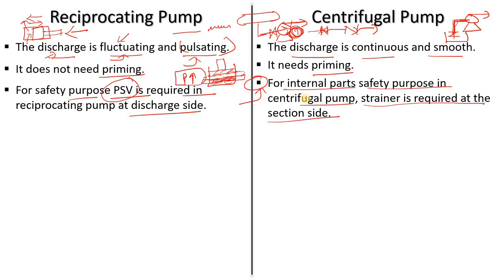In a centrifugal pump, a strainer is used at the suction side to remove foreign particles from the fluid so dust or particles don't enter the impeller or casing and damage them. Different strainer types are used: Y-type, bucket-type, conical-type, and straight-type strainers.